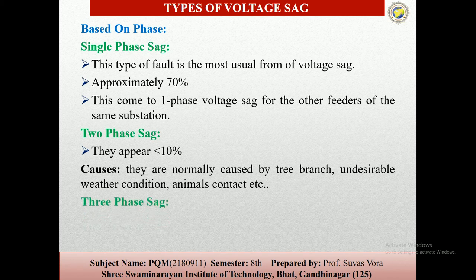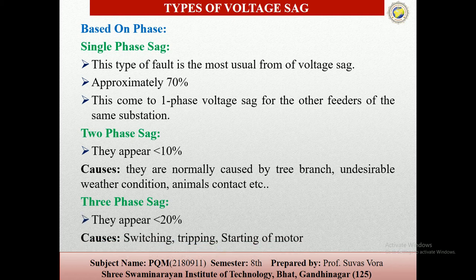Then the three phase sag is a very rare fault in our power system, less than 20%, caused by switching, tripping, starting of motors and so on, or a triple line fault in our power systems.